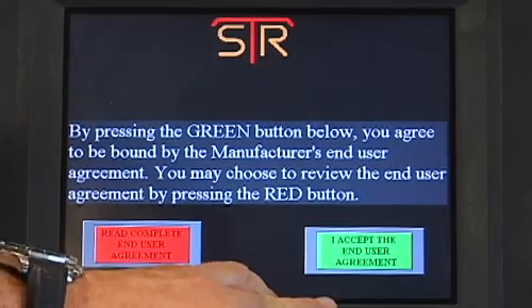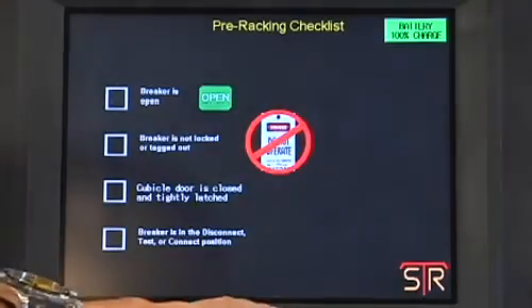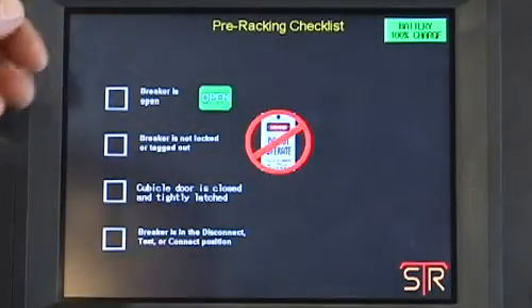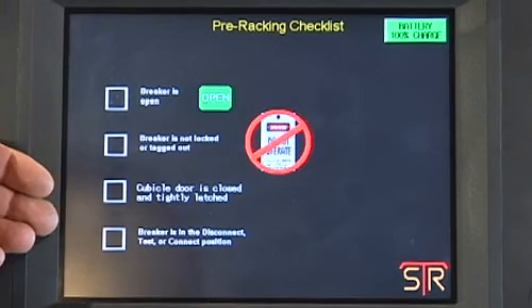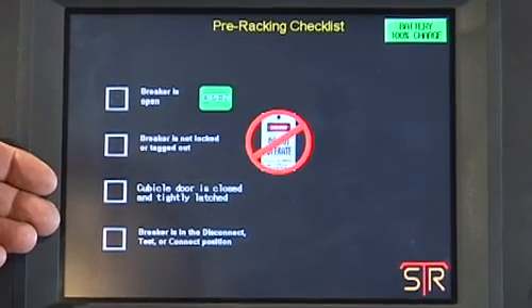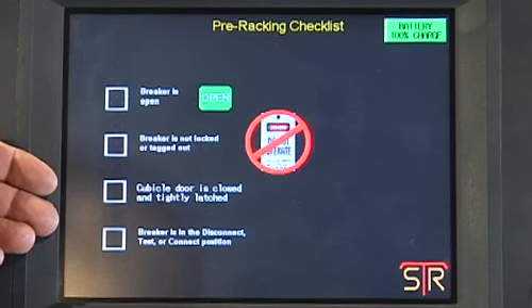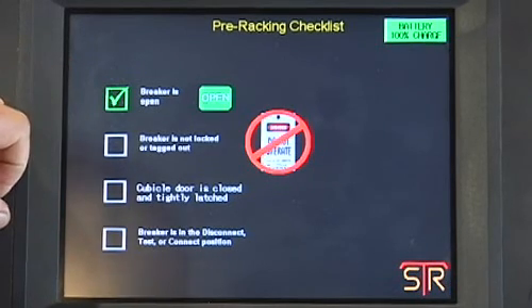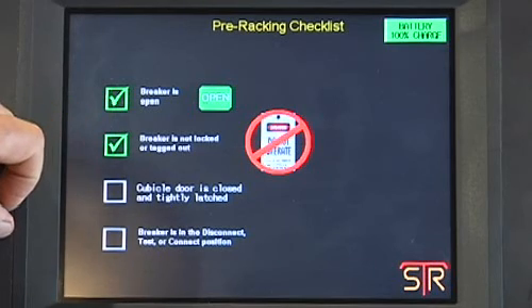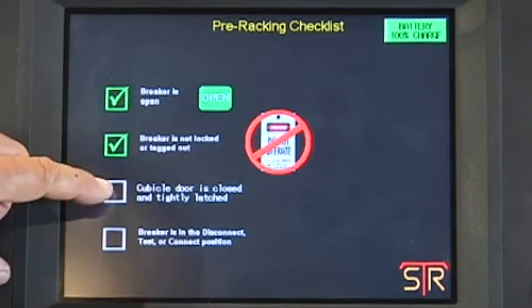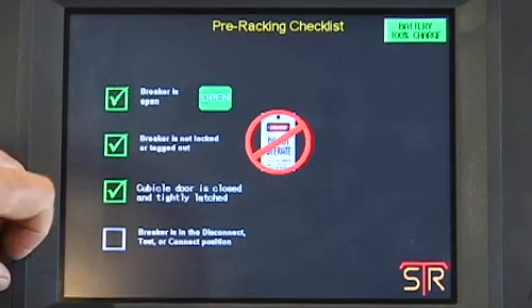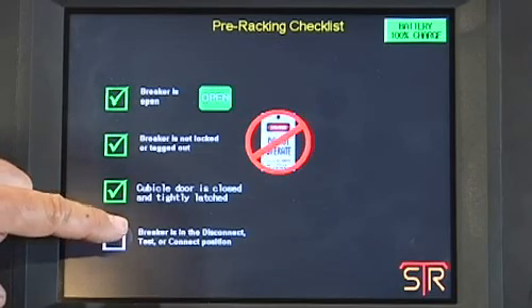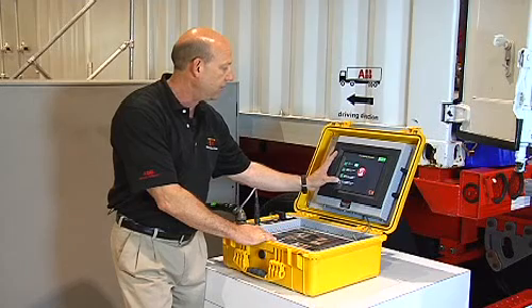We have our application software user agreement. The pre-racking checklist, which is standard for all applications. It's a reality checkpoint for the operator to verify that the breaker is open. They've checked that it's not in a safety condition, lockout, tagout, that the breaker door is closed and latched, and that we know the breaker is in a position to either disconnect, test, or connect.